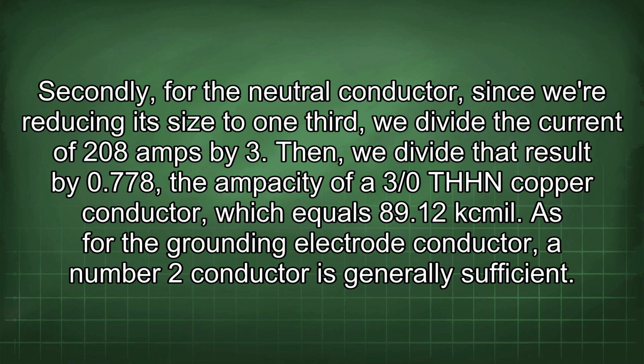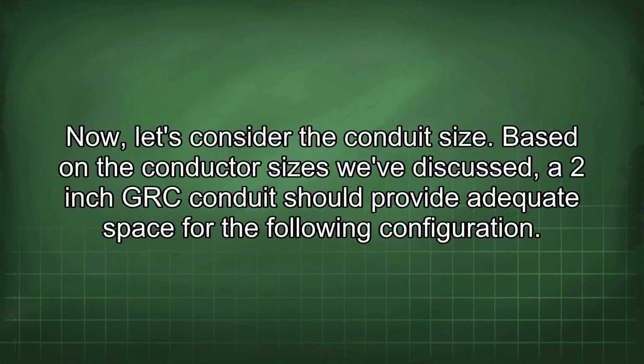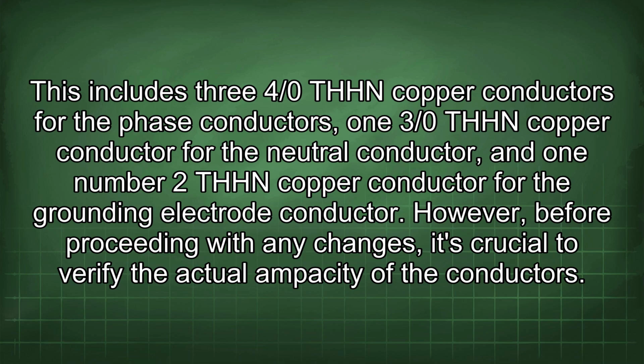As for the grounding electrode conductor, a number 2 conductor is generally sufficient. Now, let's consider the conduit size. Based on the conductor sizes we've discussed, a 2-inch GRC conduit should provide adequate space for the following configuration. This includes 3 4/0 THHN copper conductors for the phase conductors, 1 3/0 THHN copper conductor for the neutral conductor, and 1 number 2 THHN copper conductor for the grounding electrode conductor.